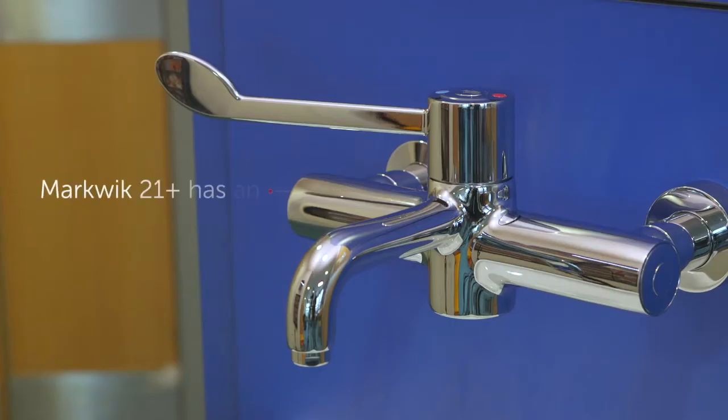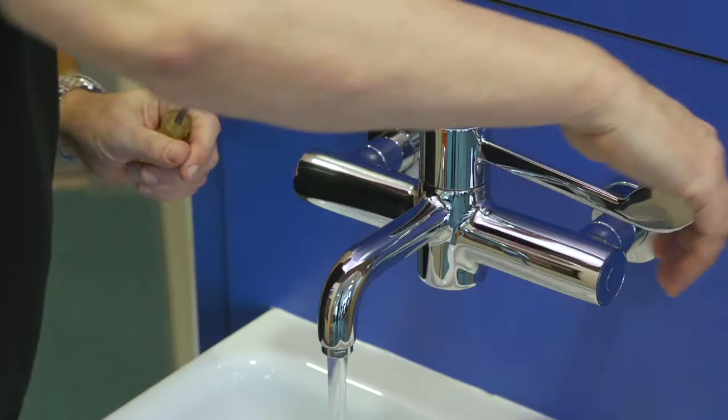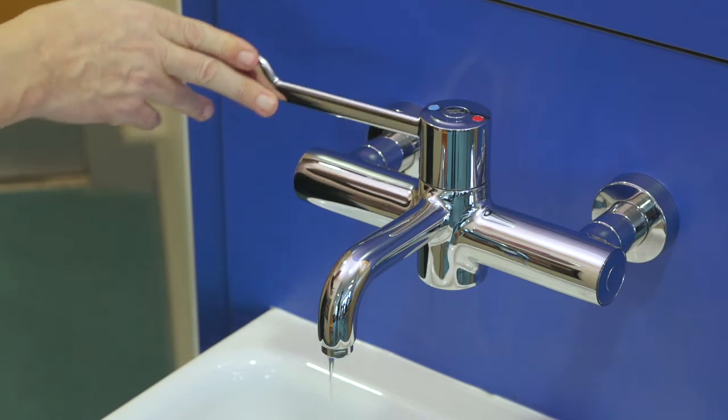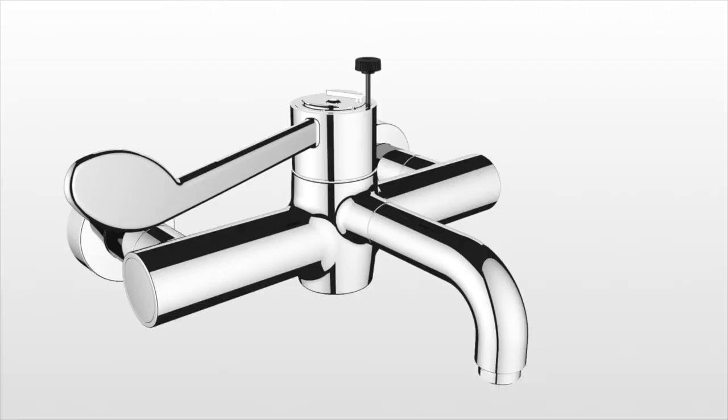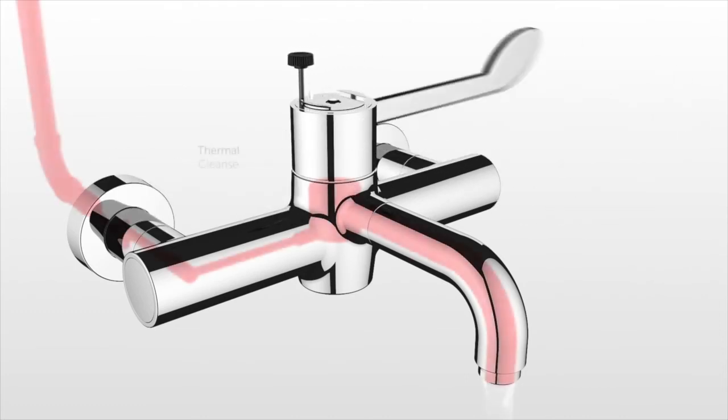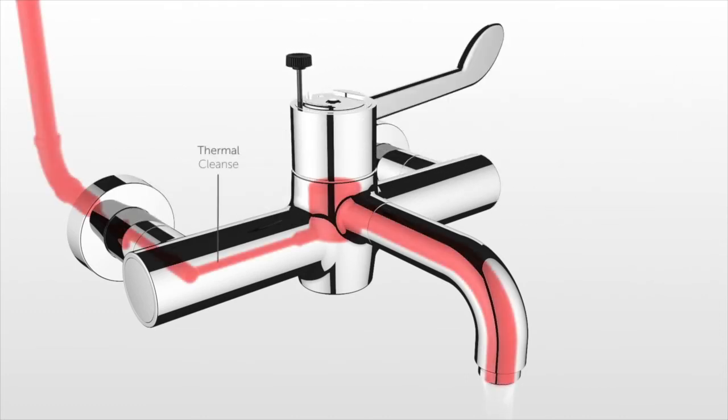Markwik 21+ uses an integral thermostat set close to the point of delivery to reduce dead legs. A self-draining spout evacuates any water remaining after use. Our latest cartridge has a built-in thermal cleanse feature for easy thermal disinfection, and the actively insulated body ensures the fitting is always safe to touch.